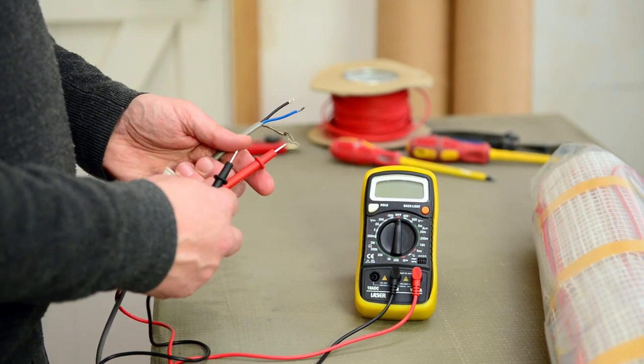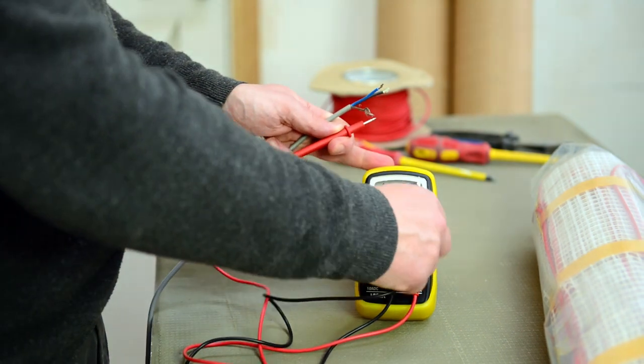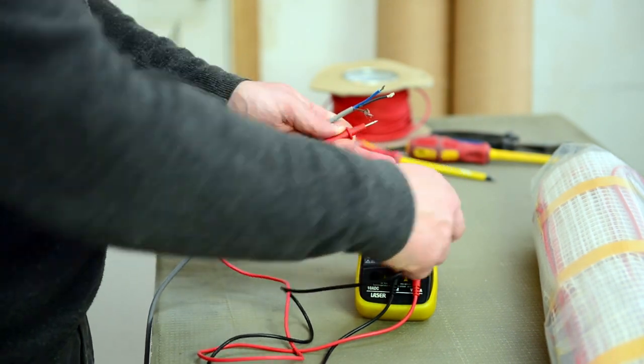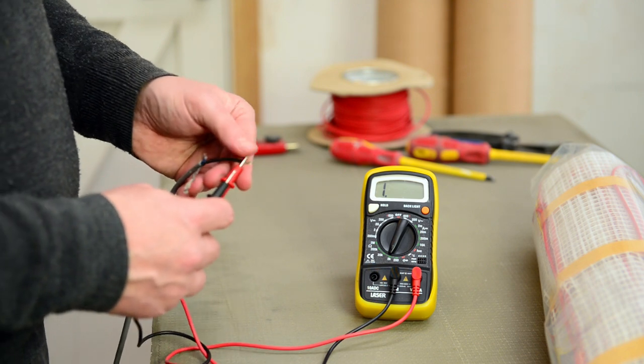Before you install your mat or cable system, you need to do a resistance reading. Set the electric meter to 2000 ohms and first check across the live.